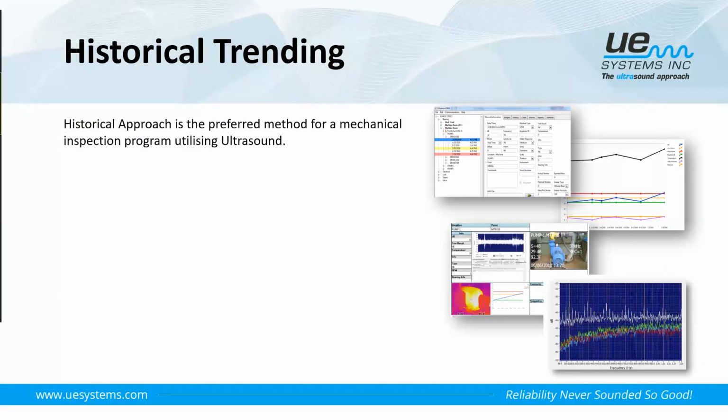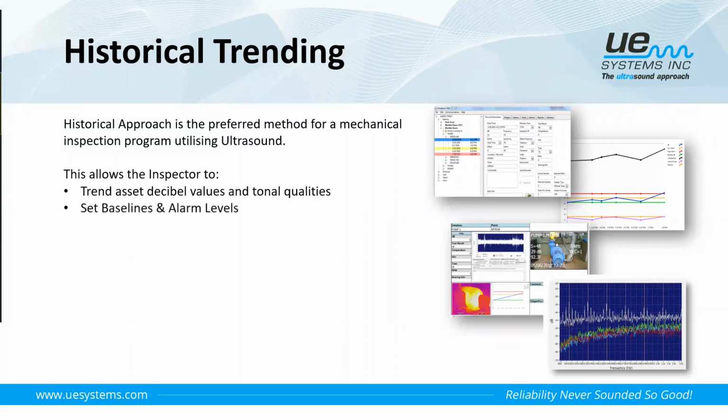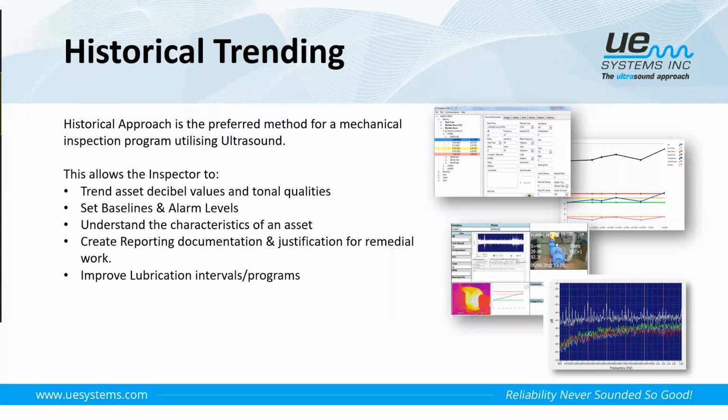So the historical approach is probably the most preferred method for a mechanical inspection program with ultrasound on a site, because we get to understand the health of our assets over a period of time. So this allows the inspector to trend our asset decibel values and tonal qualities over a period of time. It enables the user to set baselines and alarm levels, and I will cover those two subjects shortly. We get to understand the characteristics of our assets. We can actually understand how they behave by the way that they talk to us.